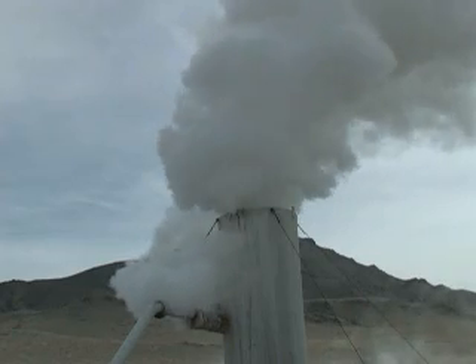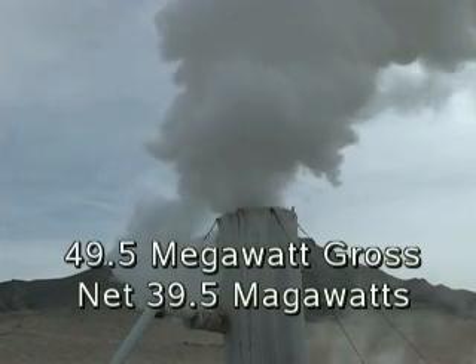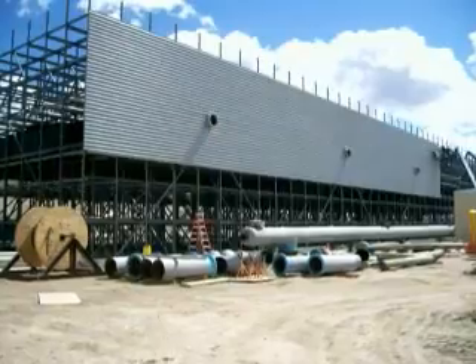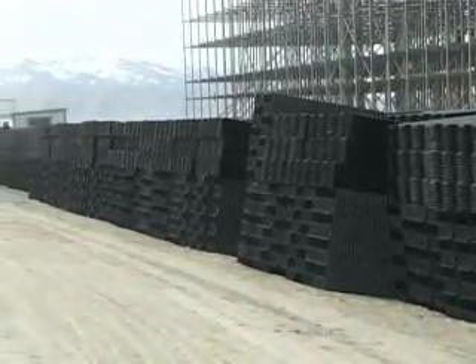With production drilling completed, there are enough megawatts to feed the geothermal plant, rated at 49.5 megawatt gross and a net of 39.5 megawatts. The cooling tower is a plastic structure with fill material all around it. Basically, when the water goes up to the top, it splashes down, hits the fill, and splashes again so that the air being sucked in gets more contact, making the cooling process more efficient.